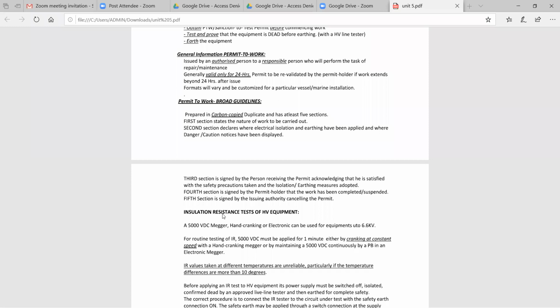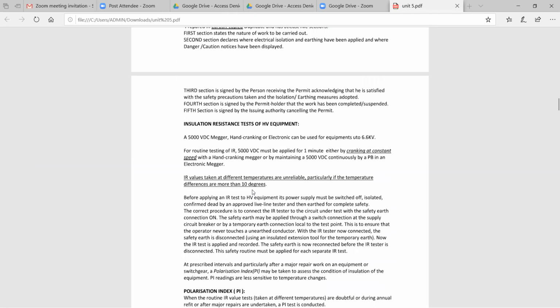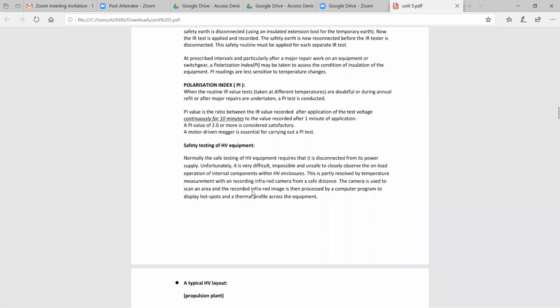The final one is the insulation test on high voltage equipment. The insulation test, otherwise called the insulation resistance test, is applied on high voltage equipment. Here the high voltage equipment can be tested. Once the test is completed, only then do we consider certain works. In this criterion, you have to consider the polarization index as well as safety testing.